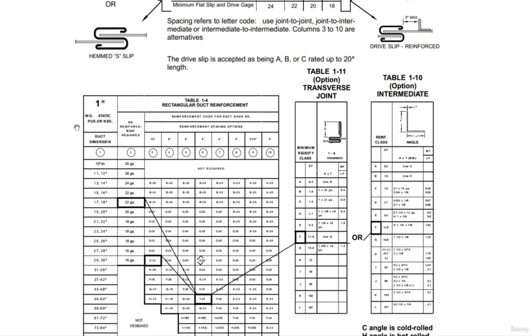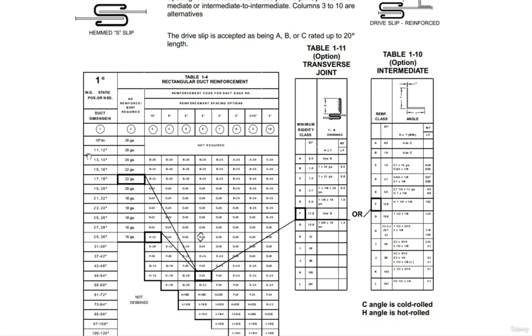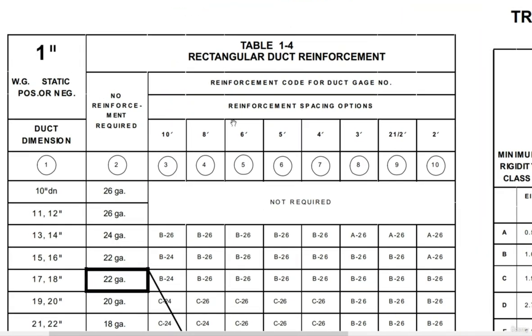Considering that the duct is operating at one-inch static pressure classification, I have Table 1.4, which is for rectangular duct reinforcement. This table can be read as follows: the first column represents the duct dimensions, and on the top left of the screen you can see the pressure classification for which duct table you will use. The second column shows the gauge of the duct required in case no reinforcement is needed. If reinforcement is not required, you use the duct gauges from the second column for sheet metal thickness. However, if reinforcement is required, you go through columns 3 to 10.